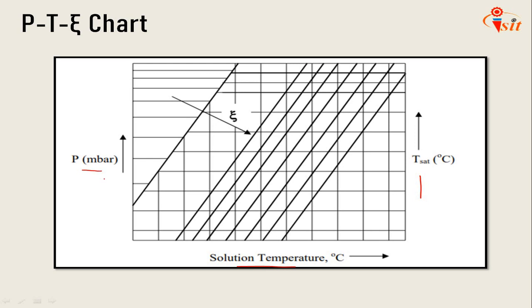The plot shows the pressure temperature values for various concentration lines, which we can also call isosters, which are linear on the Dühring plot. The Dühring plot can be used for finding the vapor pressure data and also for plotting the operating cycle.